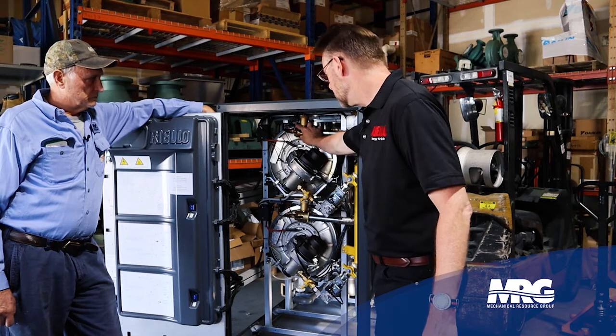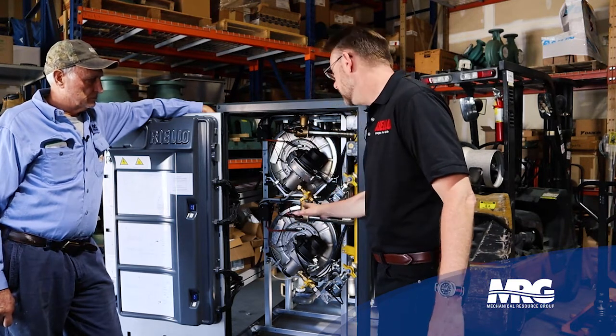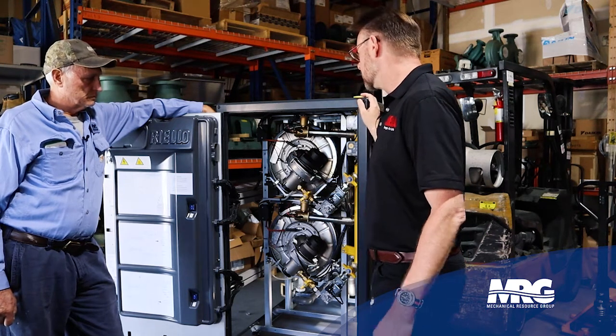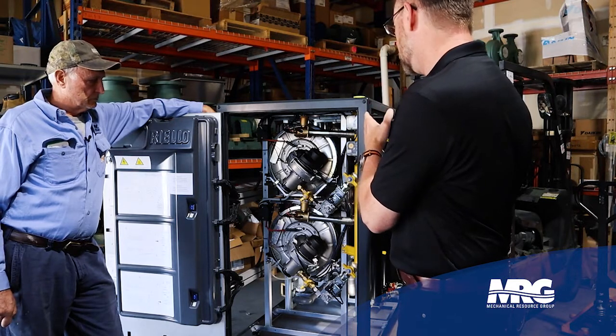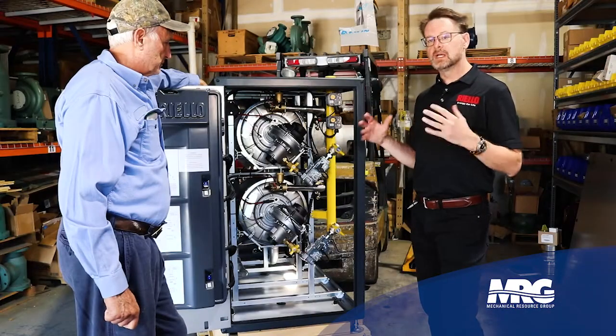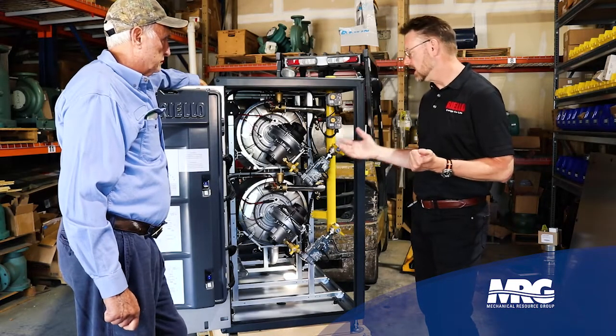If that occurred here, it would not occur here, and we would have at least some capacity available with the array. If it occurs back on the header and takes on that low water cutoff, we would have a common failure and we would have no capacity. So depending on where that air existed in this system would depend on how much capacity we lost.